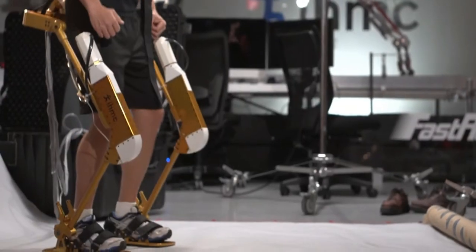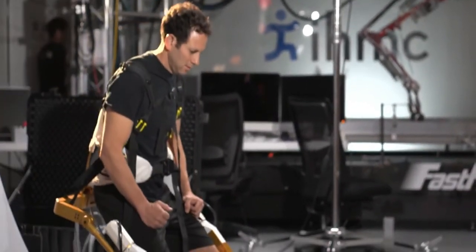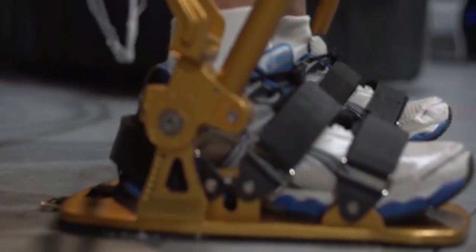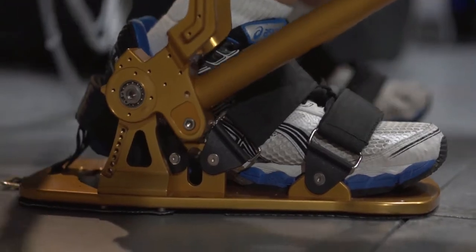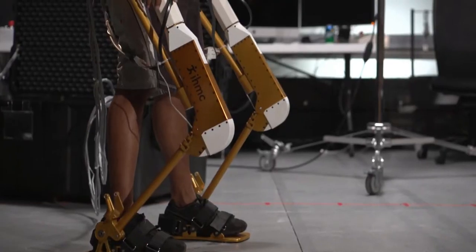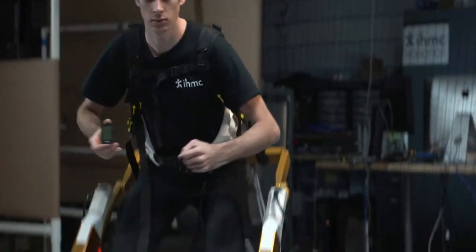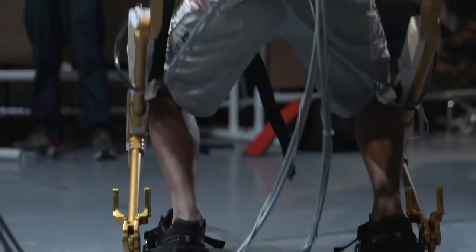It's actually called the Grasshopper — we call it that because the legs extend kind of like grasshopper legs, with this large bend in them. The motivation to design it that way was so that it only touches the user at the feet and around the torso, eliminating the cuffs around the thigh and shin, and also eliminating the need to make adjustments for different users. So it's kind of a one-size-fits-all, which is really nice up to a certain height range.